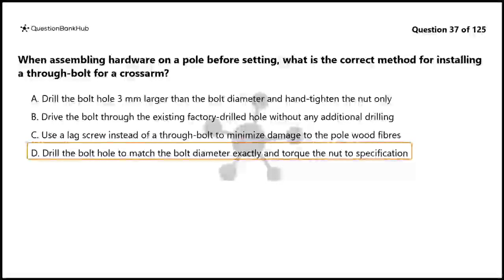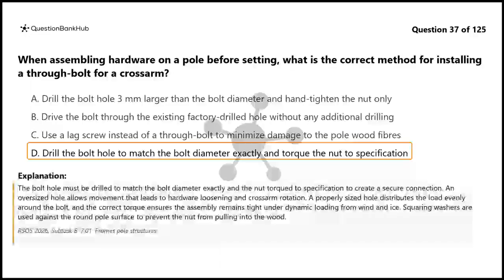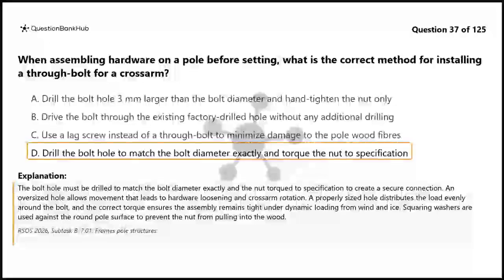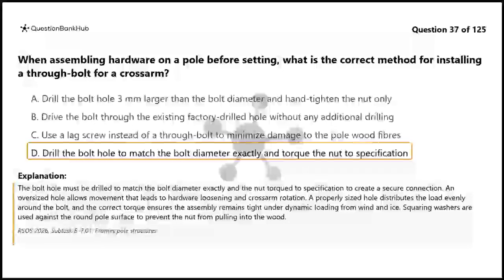The correct answer is D. The bolt hole must be drilled to match the bolt diameter exactly and the nut torqued to specification to create a secure connection. An oversized hole allows movement that leads to hardware loosening and crossarm rotation. A properly sized hole distributes the load evenly around the bolt, and the correct torque ensures the assembly remains tight under dynamic loading from wind and ice. Squaring washers are used against the round pole surface to prevent the nut from pulling into the wood.